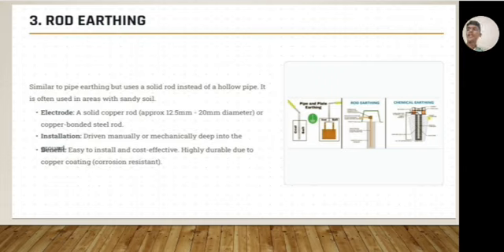Third point, rod earthing. Similar to pipe earthing but uses a solid rod instead of a hollow pipe. It is often used in areas with sandy soil. First point, electrode. A solid copper rod or copper bonded steel rod. Second point, installation. Driven manually or mechanically deep into the ground. Third point, advantage. Easy to install and cost effective, highly durable due to copper coating.